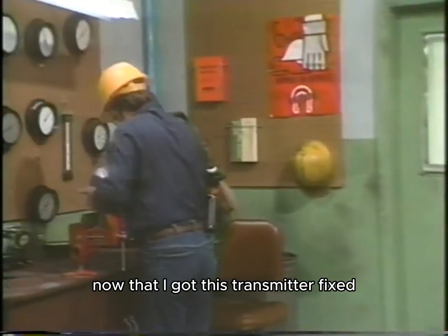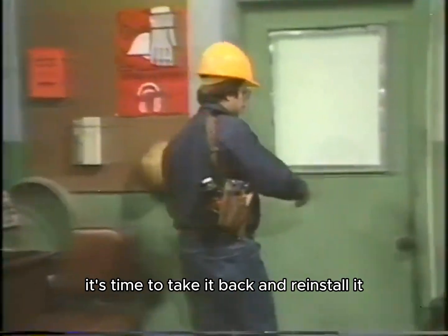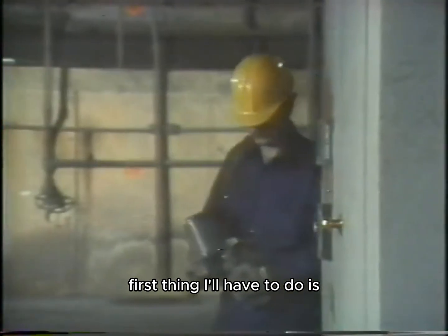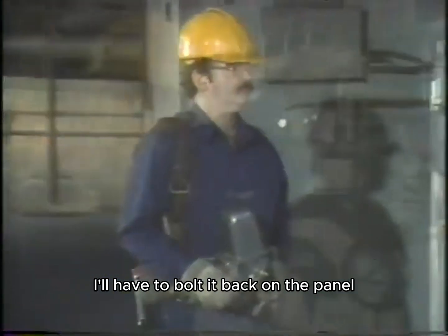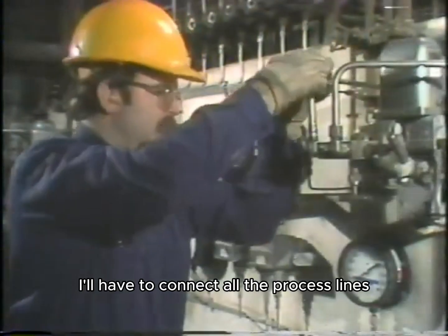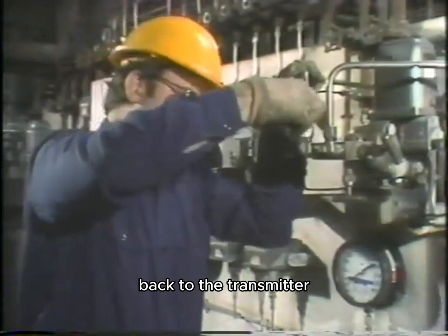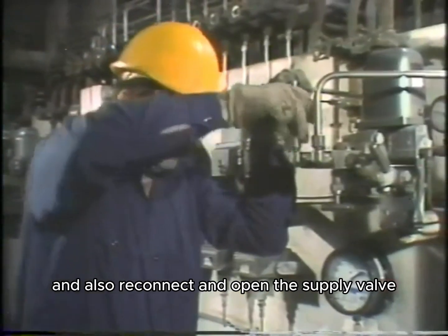Now that I got this transmitter fixed, it's time to take it back and reinstall it. First thing I'll have to do is put the transmitter back in place. I'll have to bolt it back on the panel. I'll have to connect all the process lines back to the transmitter and also reconnect and open the supply valve.